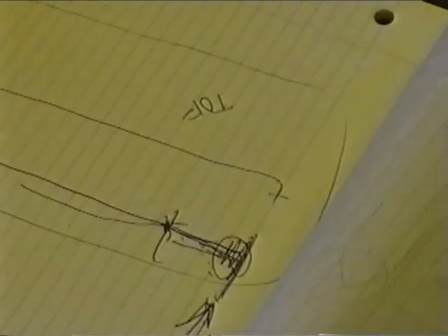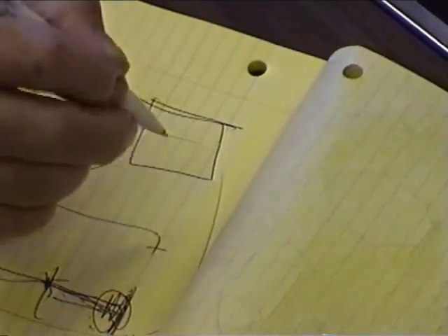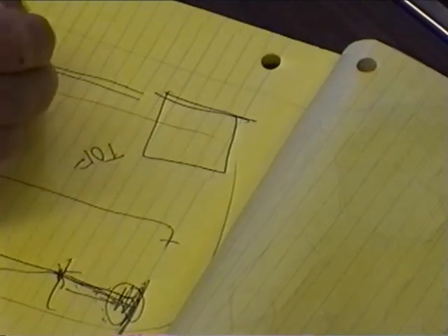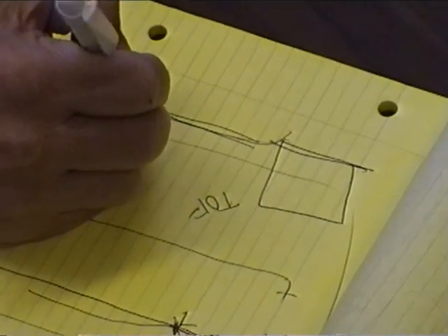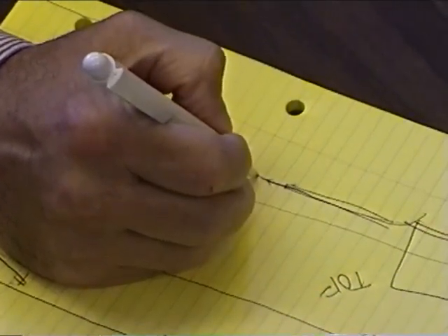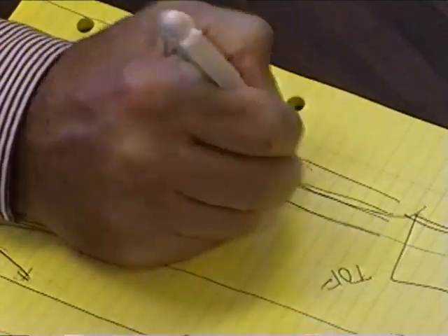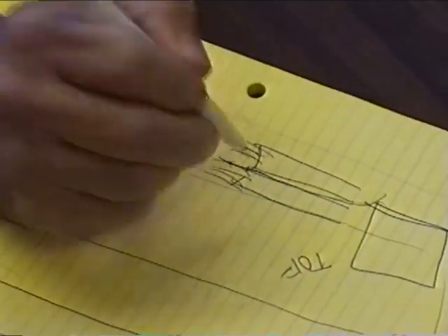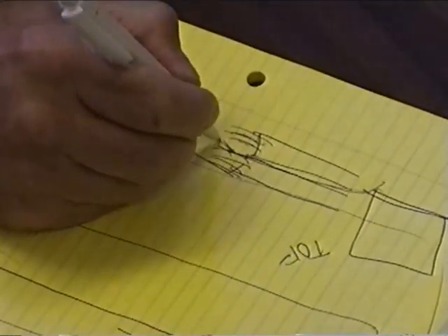Okay, the more fancy machine in there, I told you we had the QTOF, right? What it uses is electrospray to generate the ions, and I went through that very briefly. But basically, your chromatographic liquid is coming down here, this little tiny needle, and it squirts out the end. This is charged up, and then here's the mass spectrometer body per se, with this little hole in it. So this stuff is squirting out of here, and around it you have this torrent, this hurricane of hot helium gas, nitrogen gas coming along here that helps to atomize this.